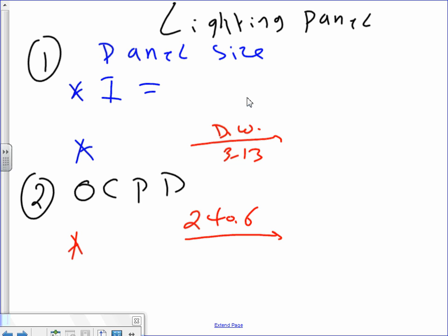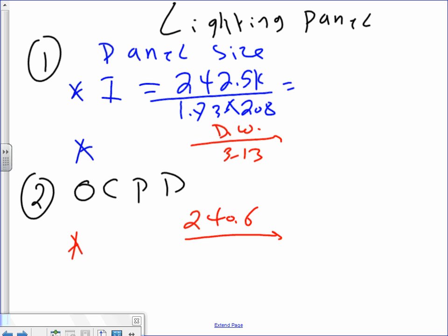We do have time here, guys. Let's knock out the lighting panel quick, because with the lighting panel we're now repeating ourselves. You guys are becoming experts now. Let's do the lighting panel, shall we? Okay, lighting panel, guys. The load for the lighting panel was 242.5 kVA. Divide this by 1.73 times 208. That will get you a healthy 674 amps. Take yourself to 674, go to the panel table. That'll get you an 800 amp panel.